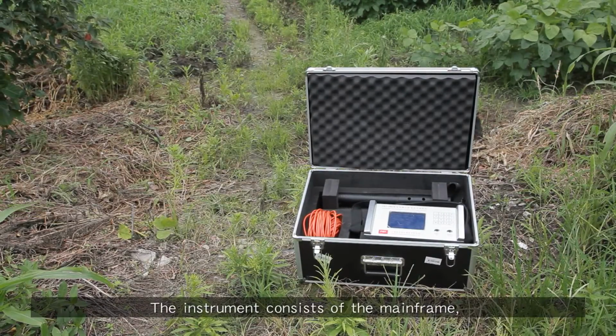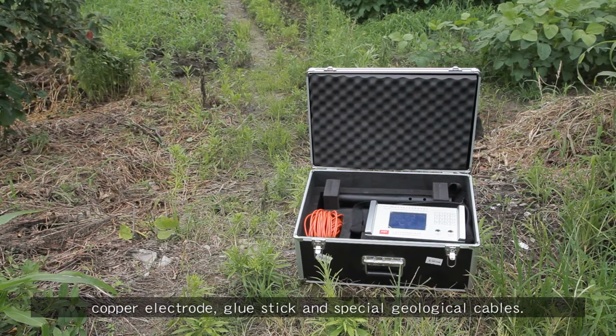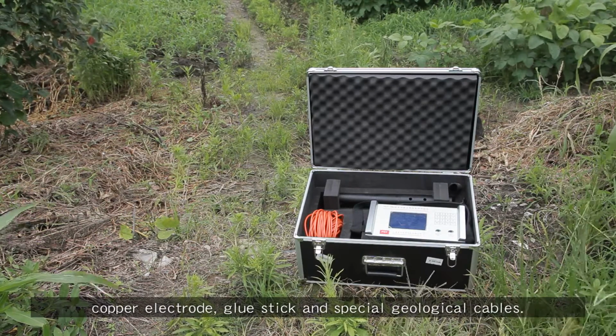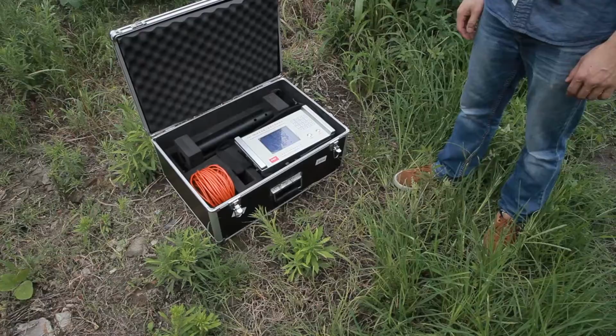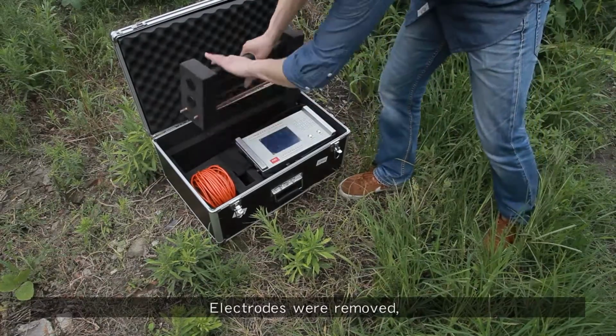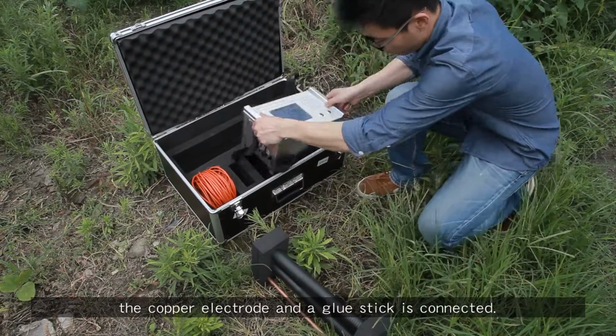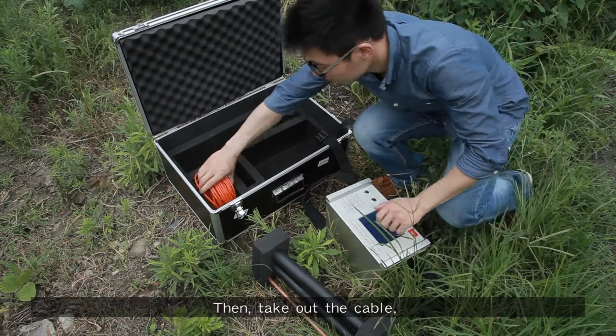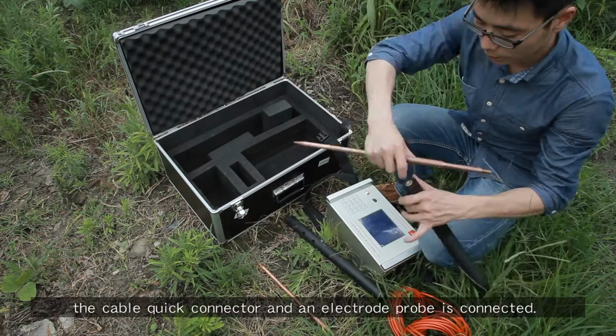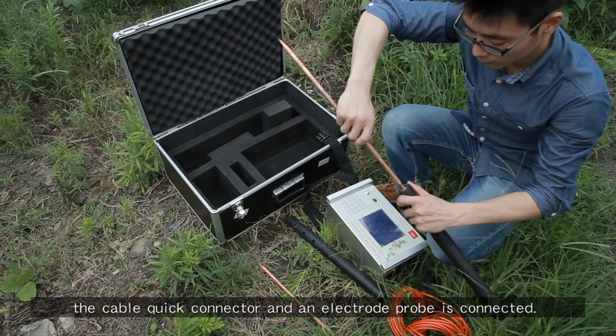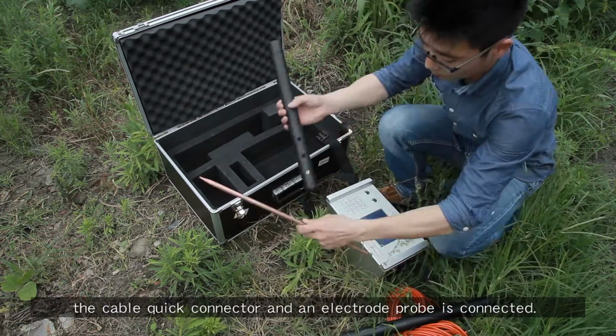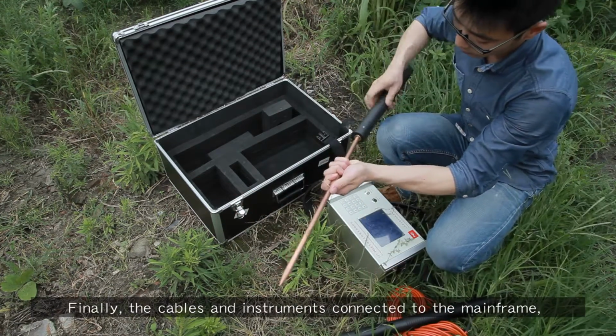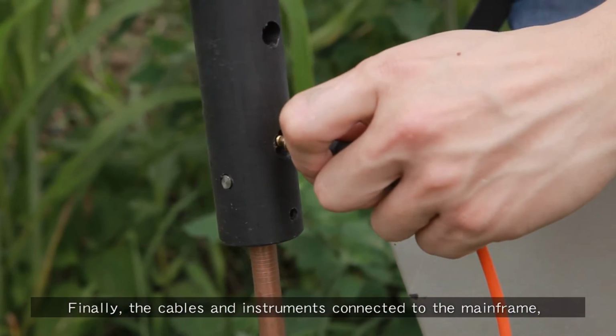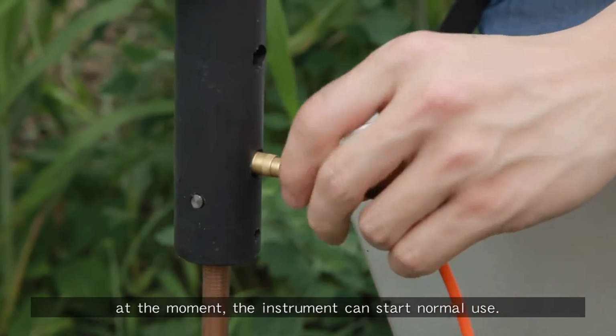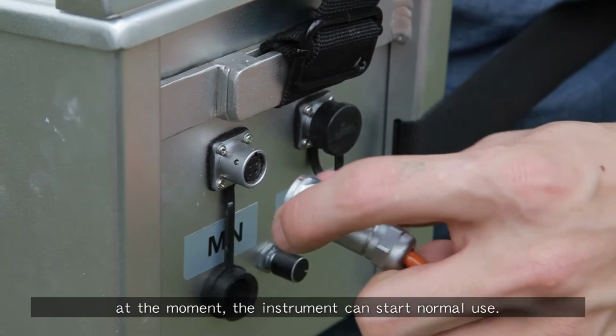The instrument consists of the mainframe, copper electrode, glue stick, and special geological cables. The electrodes are removed, and the copper electrode and glue stick are connected. Then take the cable quick connector and connect an electrode probe. Finally, connect the cables and instruments to the mainframe. At this point, the instrument can start normal use.